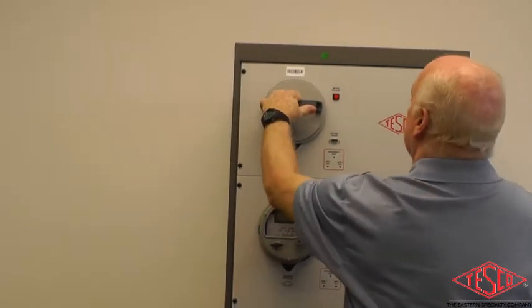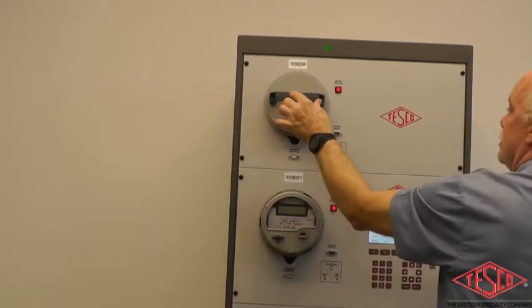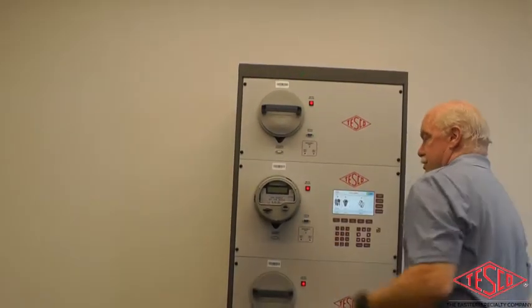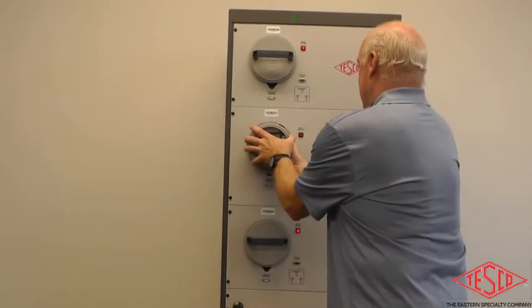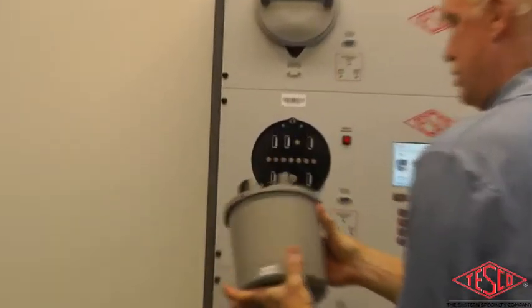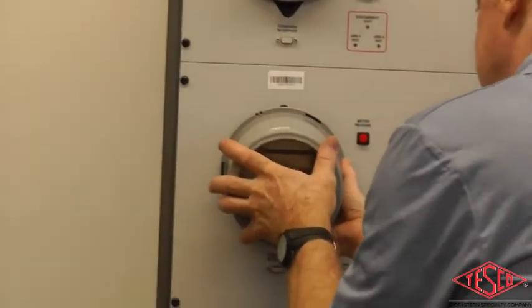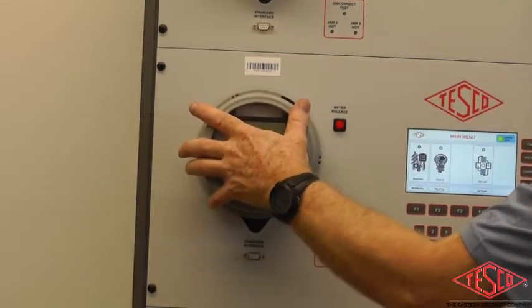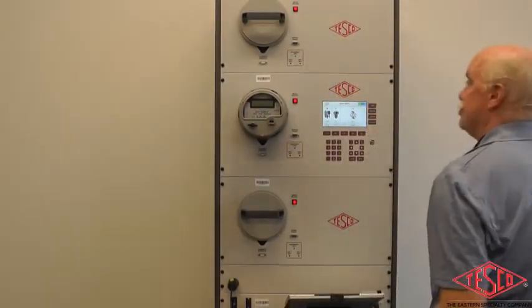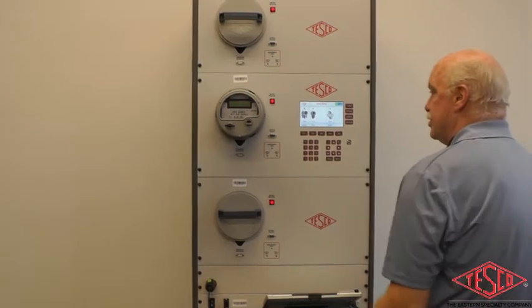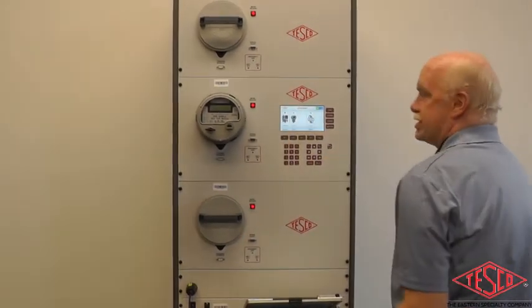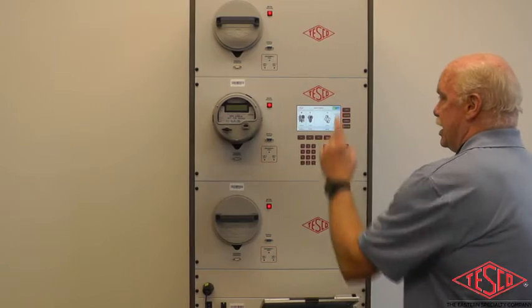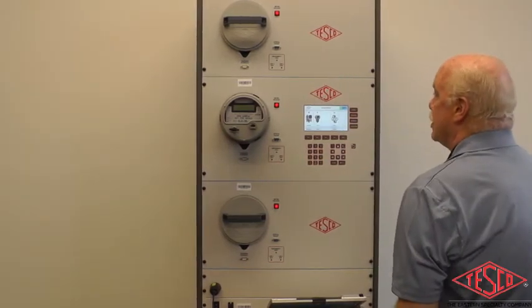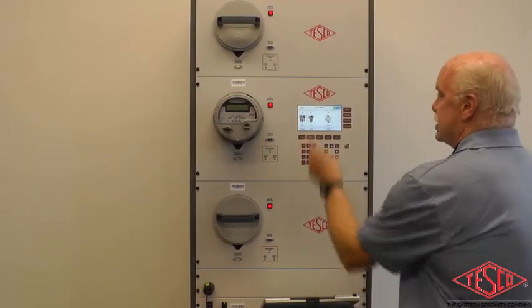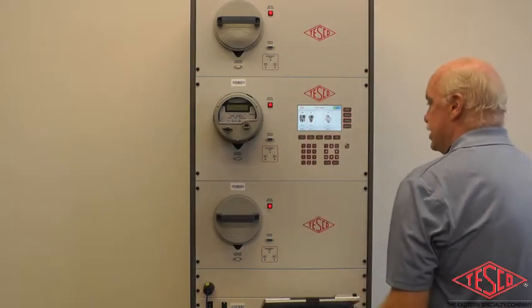There you go. And then the light will blink and now it's closed. The same thing with the meter. Line it up, push it in. Very simple, works great. So in order to run a meter, you need to have all the sockets, because the current circuit feeds all three sockets simultaneously, and each one has its own voltage control, so you can run disconnect tests on separate ones, as we'll get into later.